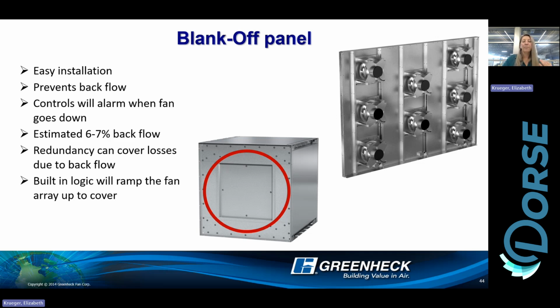There are alarms that go on when a fan does go down, or you can pop in a blank off panel there if you're waiting for a fan to come in. Then you'd have no backflow happening. So allowing some backflow, allowing the system to ramp up as opposed to spending $15,000 for dampers, is really a no-brainer. I hope that makes some sense to you guys.